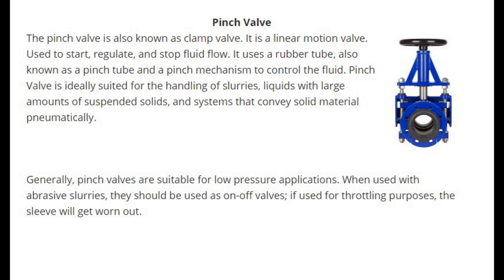The pinch valve, also known as a clamp valve, is a linear motion valve used to start, regulate, and stop fluid flow. It uses a rubber tube, also known as a pinch tube, and a pinch mechanism to control the fluid. Pinch valves are ideally suited for handling slurries, liquids with large amounts of suspended solids, and systems that convey solid material pneumatically. They are suitable for low-pressure applications. When used with abrasive slurries, they should be used as on-off valves; if used for throttling purposes, the sleeve will get worn out.